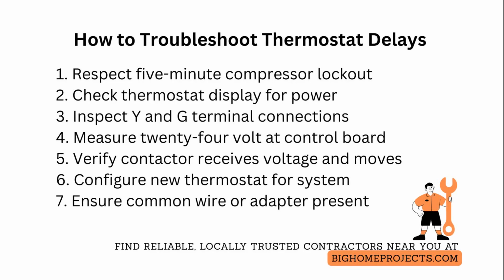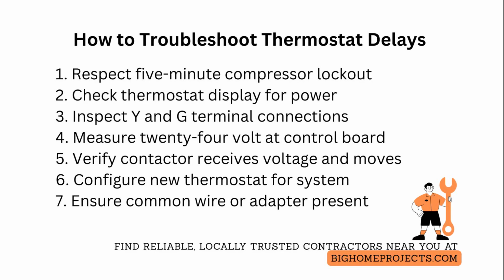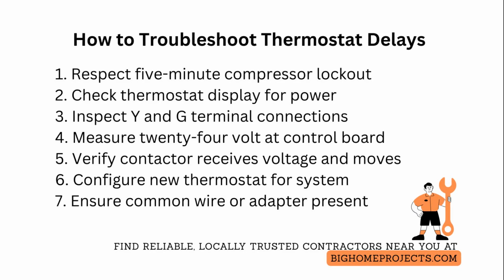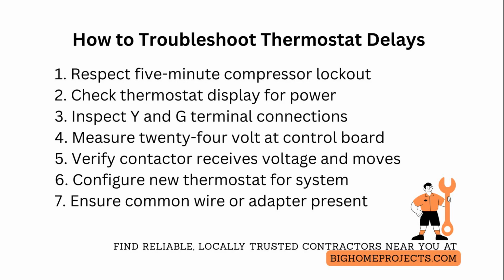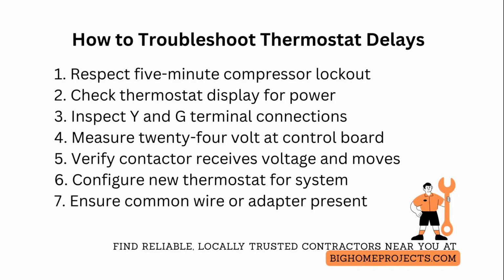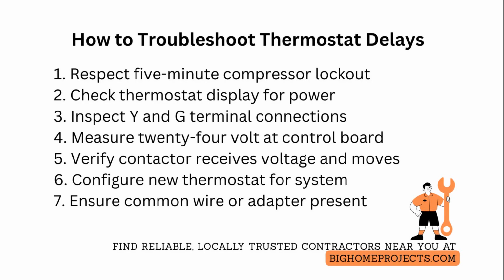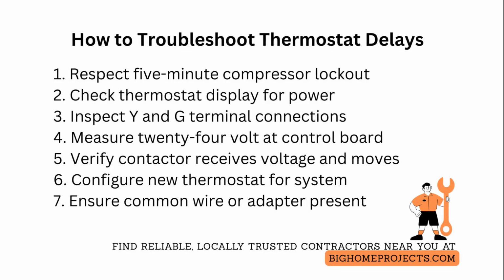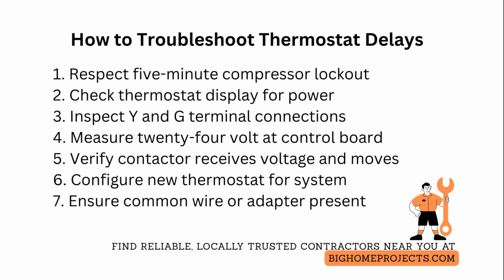For replacement thermostats, verify the new device is configured for conventional systems versus heat pump systems and set the correct fan control and stage count. Incorrect configuration can prevent a proper Y call. When smart thermostats are used, ensure the C or common wire is present or the unit has an adapter kit. Many smart units try to draw power wirelessly and cause blinking or intermittent calls if C is absent. Finally, document wire colors, terminal labels, and take a photo before disconnecting anything. This avoids miswiring on reinstallation.